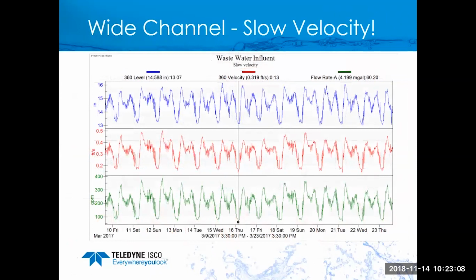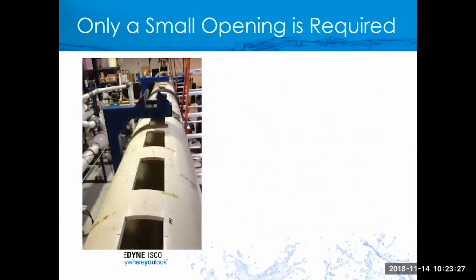Here's another one that was a wastewater influent. It's a rectangular channel, but you'll see up there, this thing is moving at 0.13 feet per second velocity. So just a crawl, even though it's a fairly large channel, that water was barely moving at night. So nothing else would read that kind of condition, easily anyway.